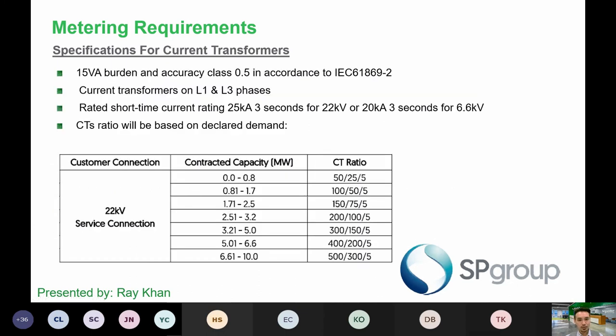Right. So here talks about the different steps of the CT ratio. So just take note, a very quick one is that for a 500/300/5 CT, it's actually much smaller in size compared to the one at the CT ratio of the 50/25/5 ratio. Okay, so the size is actually vice versa. So in terms of space planning, also price planning as well, you might want to take that into consideration, because the larger size CTs are usually the more expensive ones.